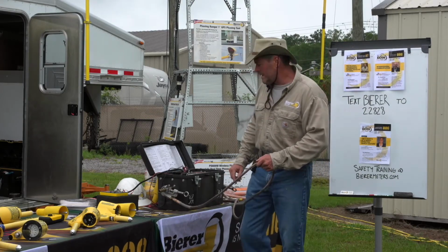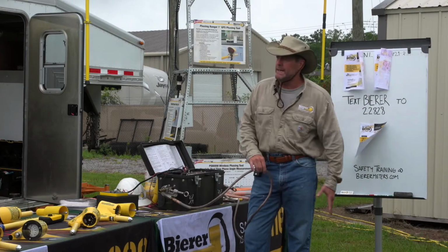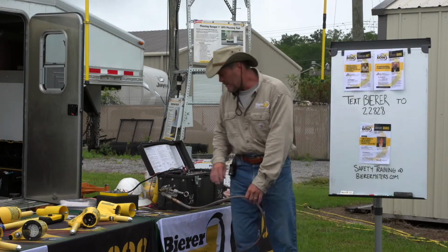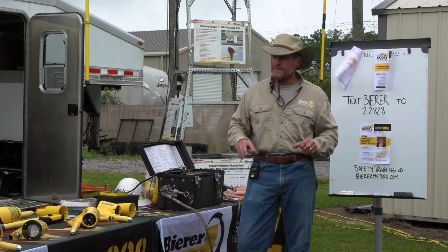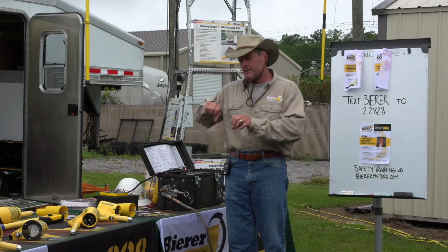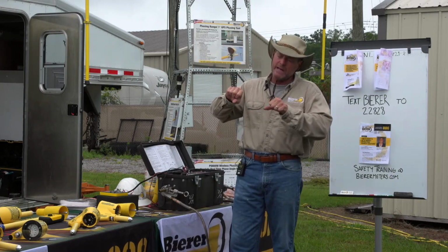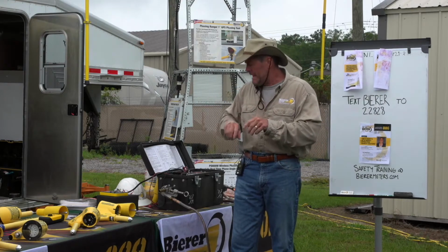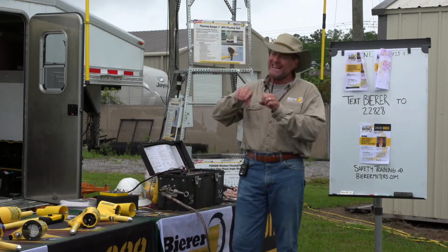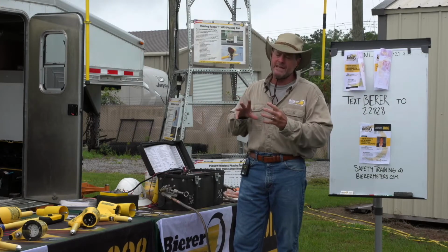So what you're going to do is also perform a mechanical test. Physically grab hold of those clamps and your cable, and make sure that crimp is nice and tight, that the cable's not loose in the crimp. Also verify that the ferrule is actually tight within that clamp, and you don't want to see any obvious loose components, like little pieces on those duck bills. As long as they pass a visual and a mechanical test, typically your TPGs, your best friend, are going to take care of you.